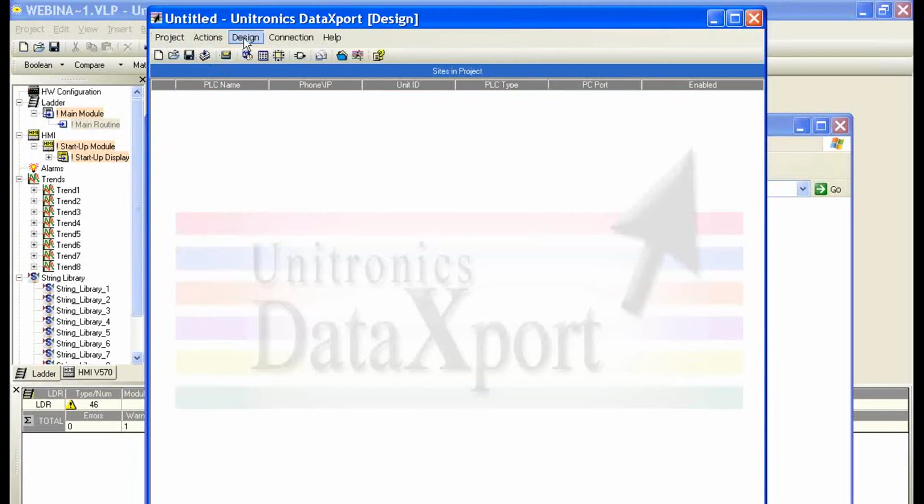And again, the benefit here is that the PLC can initiate the download. So we can use our row index, say, if we want to log information instead of on a time basis. Maybe there's some event every time a bit goes high, every time a door is open. We can't easily calculate how long it's going to take to fill a data table, but with this method, we don't have to worry about it. We can let the PLC worry and say when the data table is near full, I want it to download. We can use one of those success bits to clear out the data table after that.